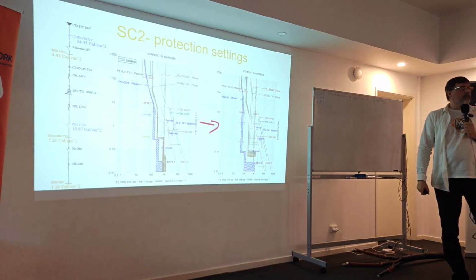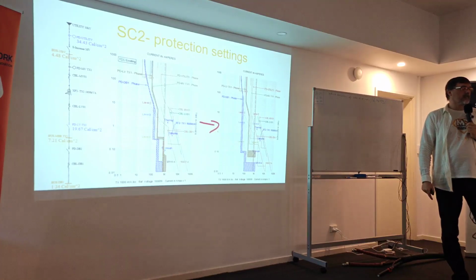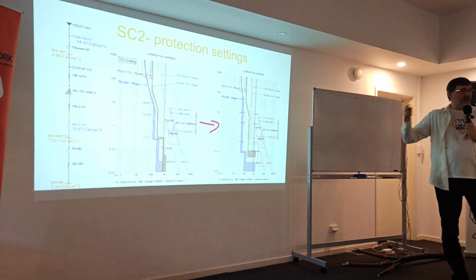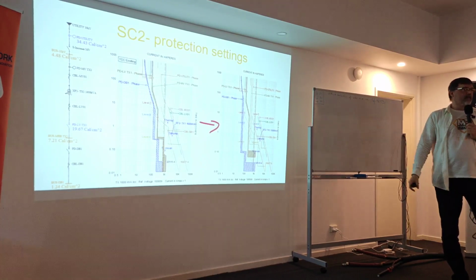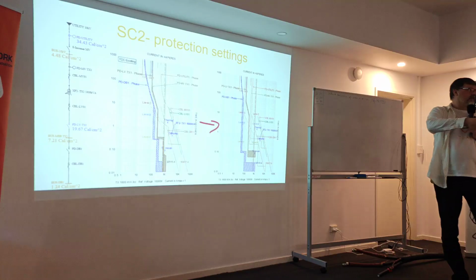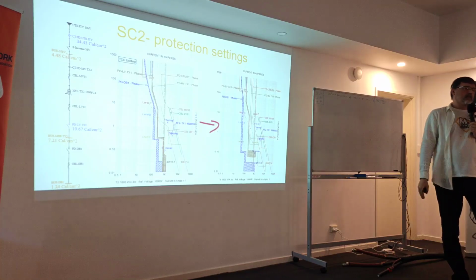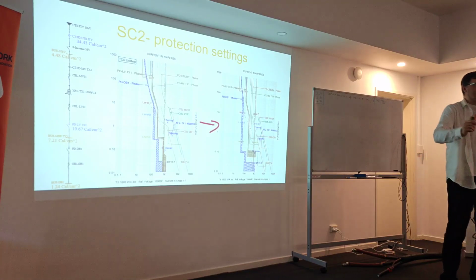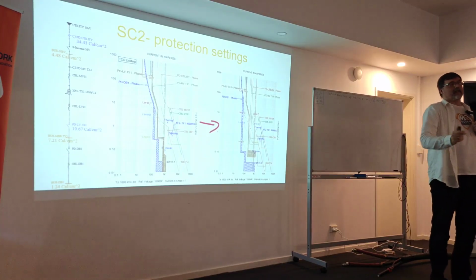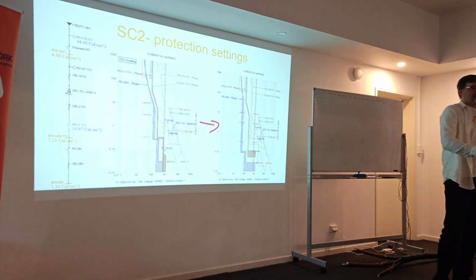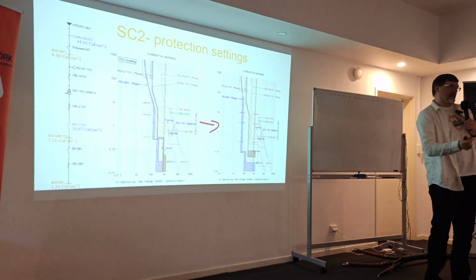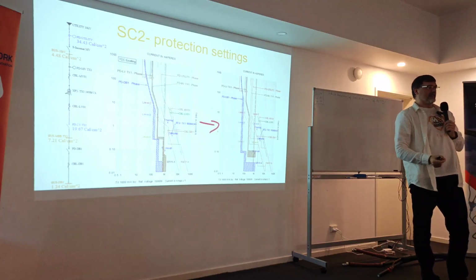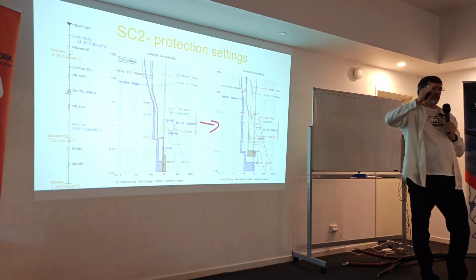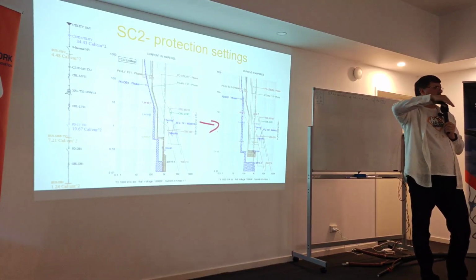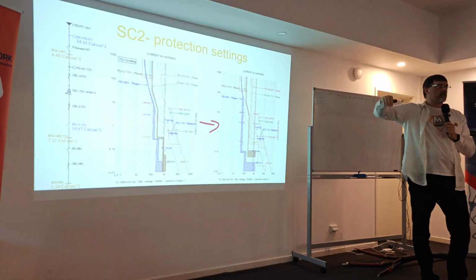Because the problem with the settings is that they are very random, and sometimes whole sites are on factory default. I found out, when I was working at Eaton, there was a manual. Eaton has a lot of things from Woodward and from SEG. They work together, and in the manual it was written factory settings. And for customers, because we had a factory, it meant that we did something. And I said, no, it means default settings. And the factory needs to have a default setting because we do the quality check, quality testing. So they just set it usually to the minimum.